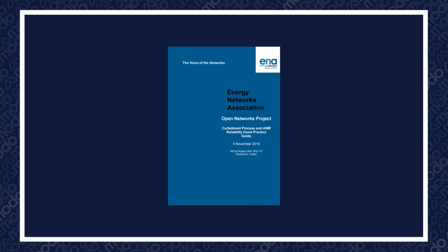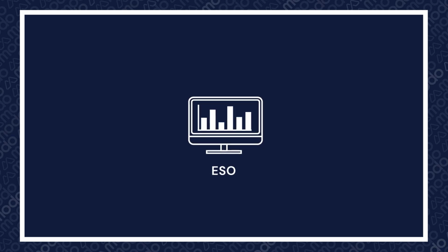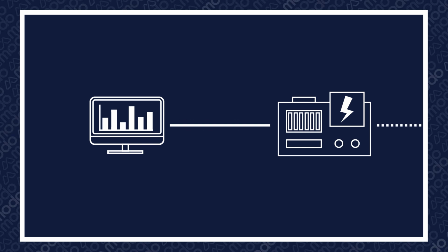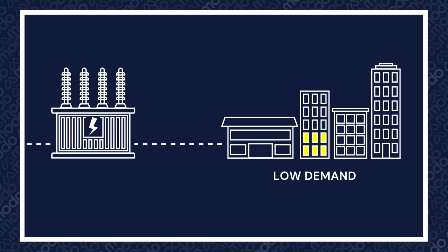To work out how much of a generator's output must be curtailed, DNOs carry out curtailment assessments. Curtailment assessments are then used by the National Grid Electricity System Operator, or ESO, as part of the process to decide whether a given generator would be a suitable participant in its balancing services. Curtailment assessments simulate ANM behaviour across specific timeframes to provide an estimate of the occurrence and severity of ANM actions on generators, including an estimation of megawatt-hour curtailment across the given time period.